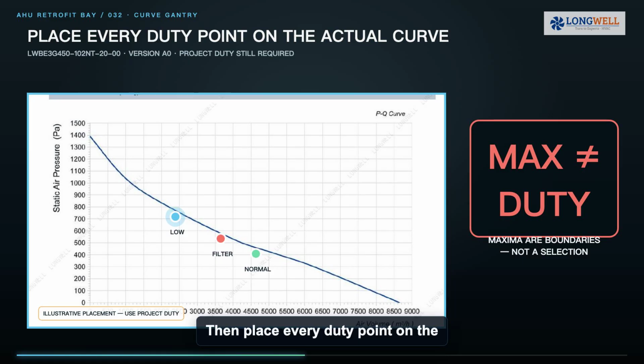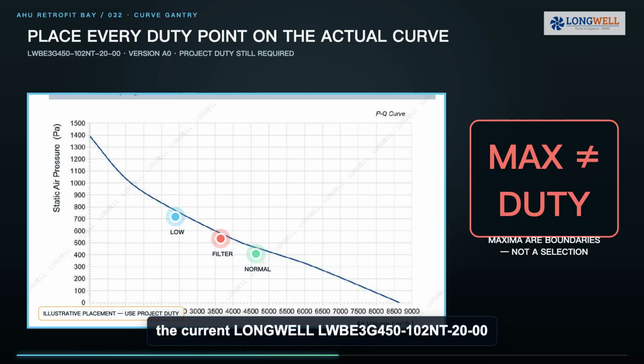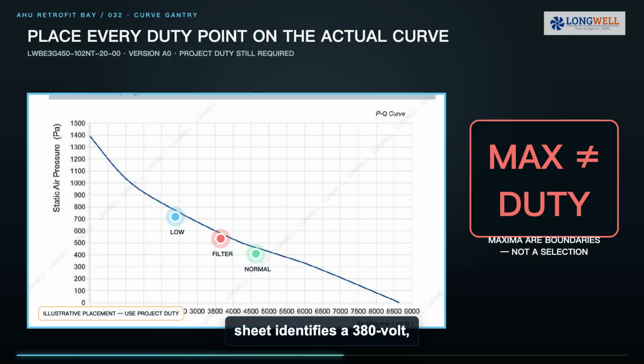Then place every duty point on the manufacturer's curve. Confirm that each point is inside the permitted operating region and check speed, input power, current, temperature and sound at that point. For example, the current Longwell LWBE3G450-102NT-20-00 sheet identifies a 380-volt, 3-phase EC backward curved fan. Its maxima are boundaries, not a retrofit selection. The project duty must be reviewed on the curve.